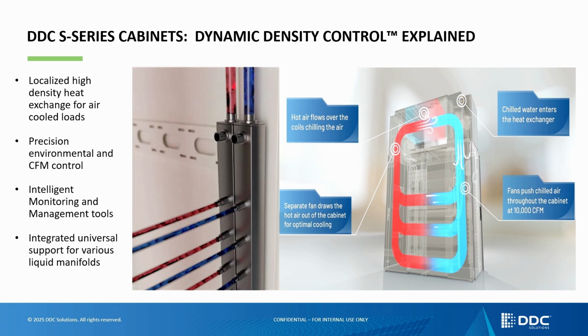To augment above 100 kilowatts, we've added liquid-to-chip integration directly into the cabinet. Since we've already got water at the cabinet level, we're working with a variety of partners to use a universal mount structure so we can put manifolds in both the front and back of the cabinet to bring that liquid-air cooling capability.